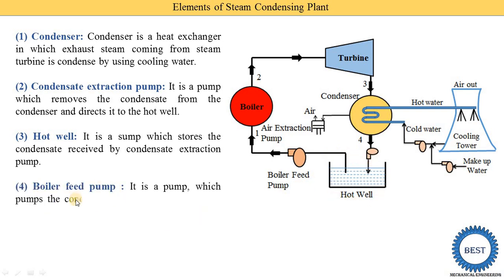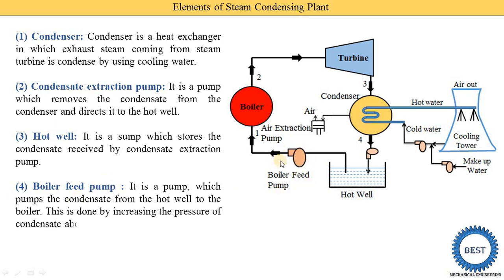The fourth component is the boiler feed pump. This pump pumps the condensate from the hot well to the boiler. The function of the boiler feed pump is to supply the water from the hot well to the boiler by increasing the pressure of the condensate above the boiler pressure.